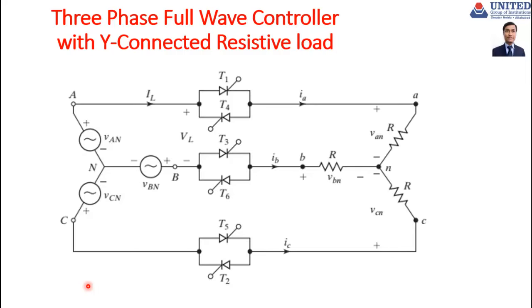As we know, when single phase AC voltage controllers are used in high power load applications, a distorted waveform of line current is produced. This distorted line current creates unbalance in the three-phase line current. Usually this unbalanced line current flows through the neutral, which must always be avoided. So three-phase AC voltage controllers should be used in high power applications in place of single phase AC voltage controllers.